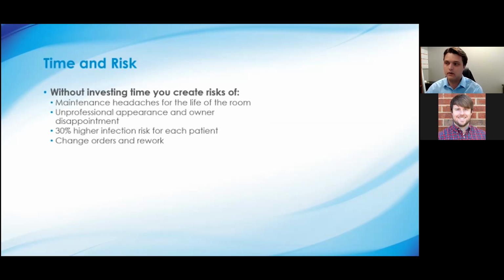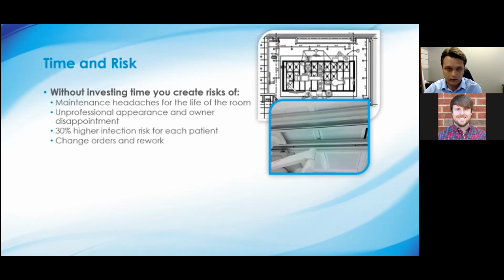When I talk about risks, I mean maintenance headaches for the life of the room. Here's a room with imaging equipment mounted on the ceiling, requiring ceiling level unistrut to support it. A mechanical designer knew about the unistrut but needed to get air in to meet code, so they packed diffusers in as tight as possible between those channels and marked it good to go. The problem is that designer was only looking at the air component and wasn't accounting for other medical devices in the space, like the imaging equipment hanging from that unistrut.